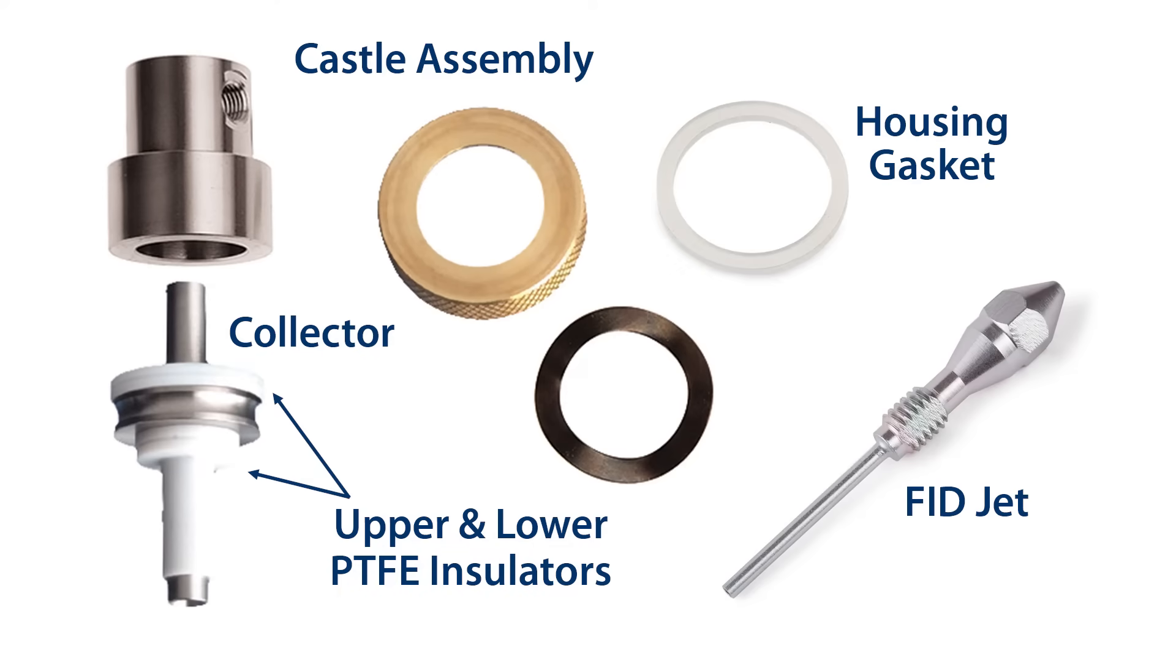If you have tried changing the jet but these problems still persist, then it's time to replace some of the FID parts. This includes the castle assembly, the upper and lower PTFE insulators, the collector, the rubber housing gasket, and the FID jet.